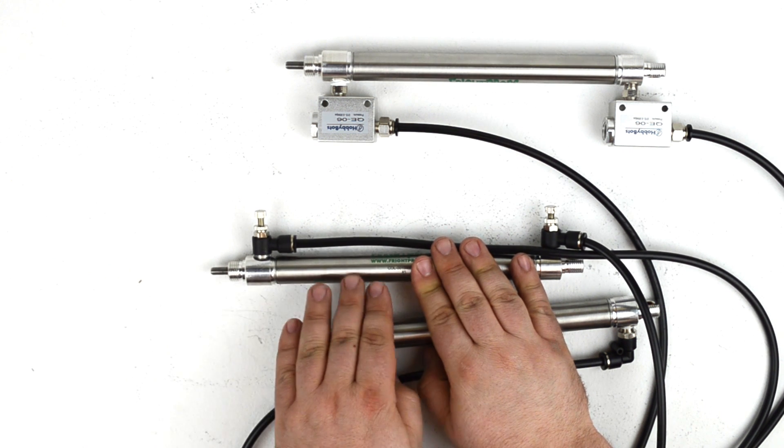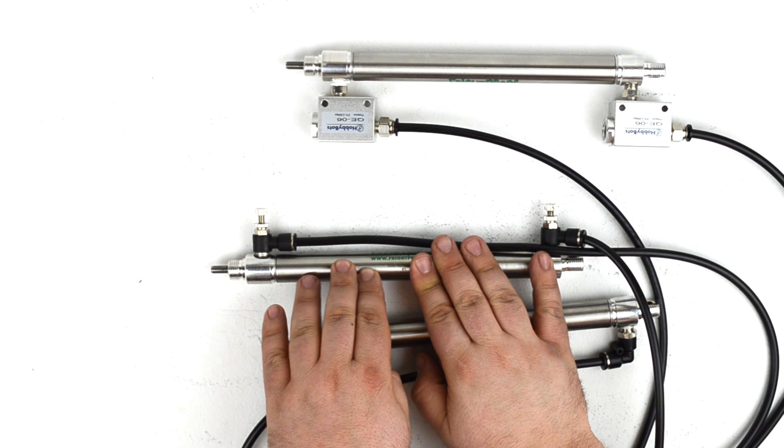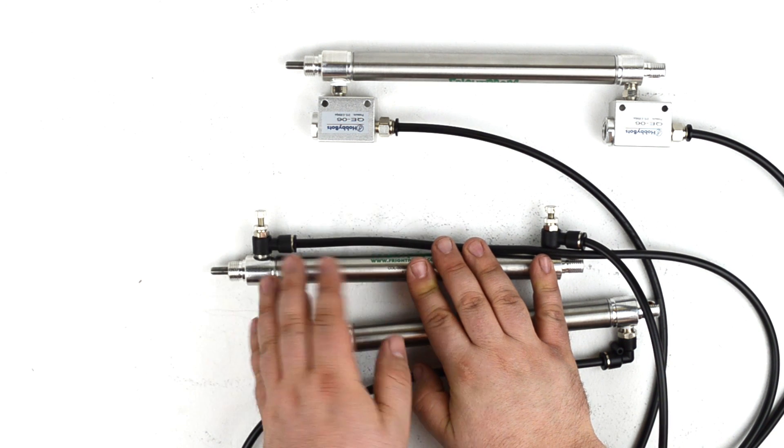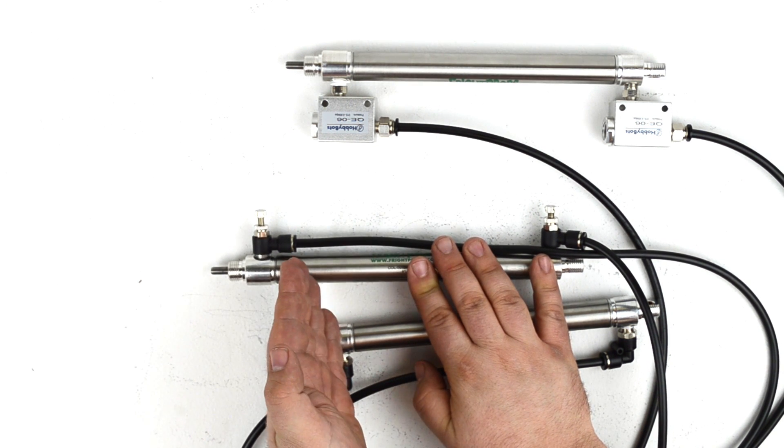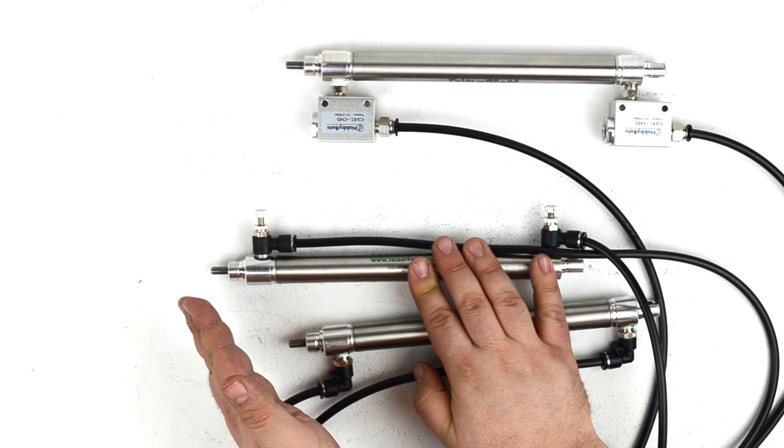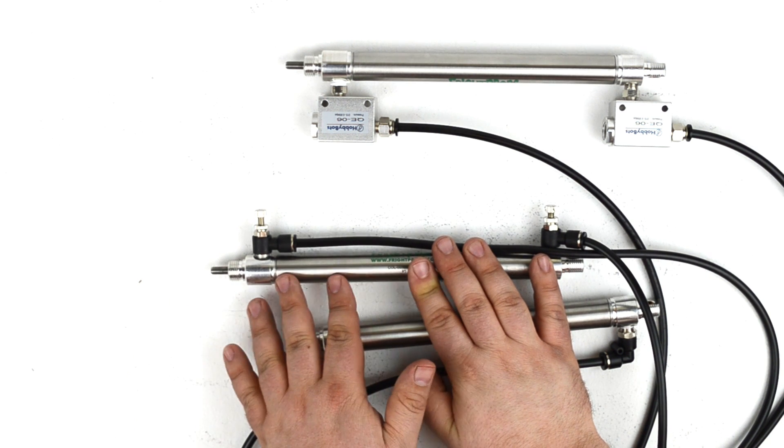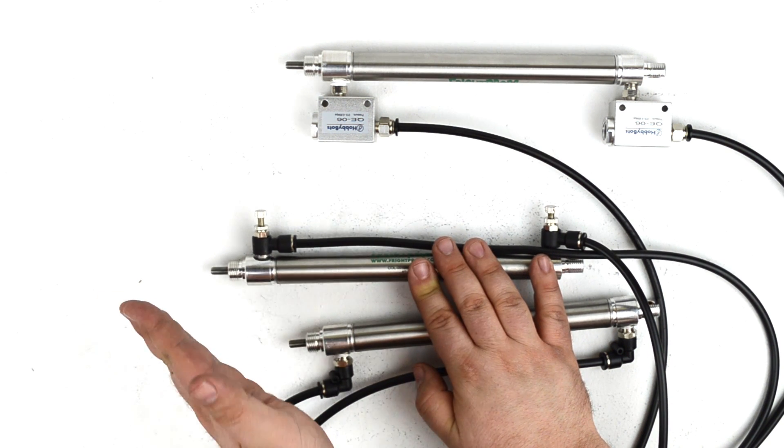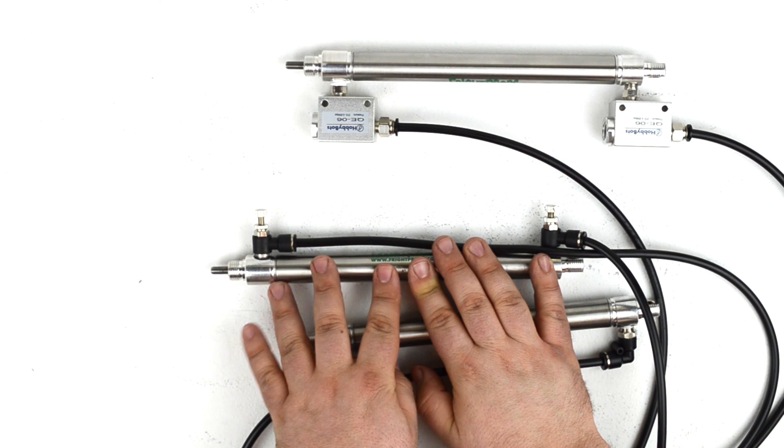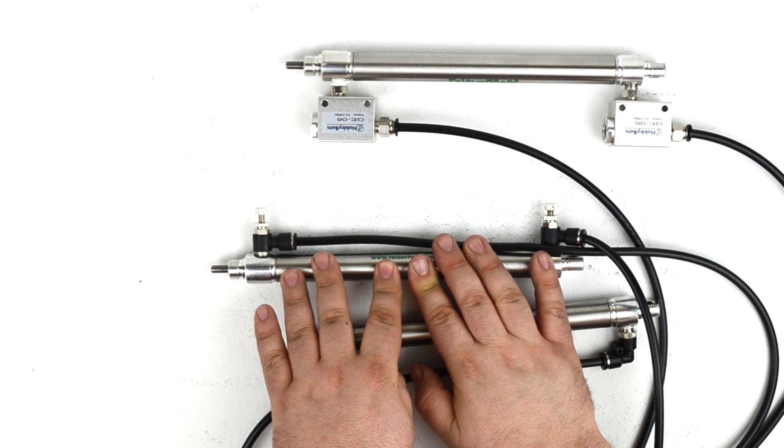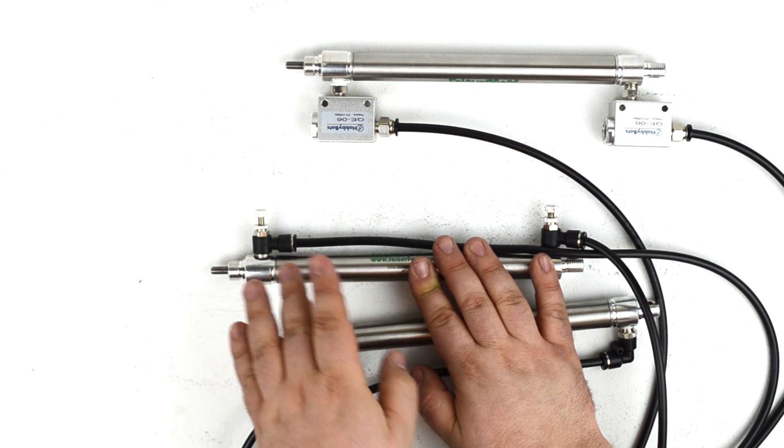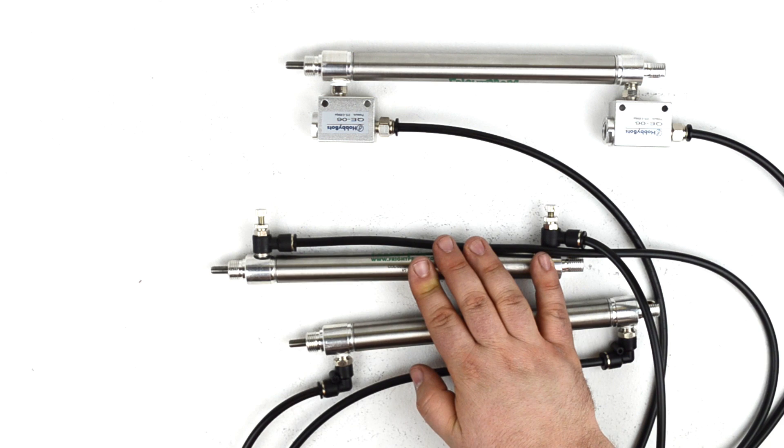One thing to note about controlling the cylinder speed is that although you can control and set the speed going in and out, you can't change it mid-stroke. So you can't have it start slow and then go fast. It's going to be set at one standard speed and that's just the speed that it's going to operate at once you have it dialed in.